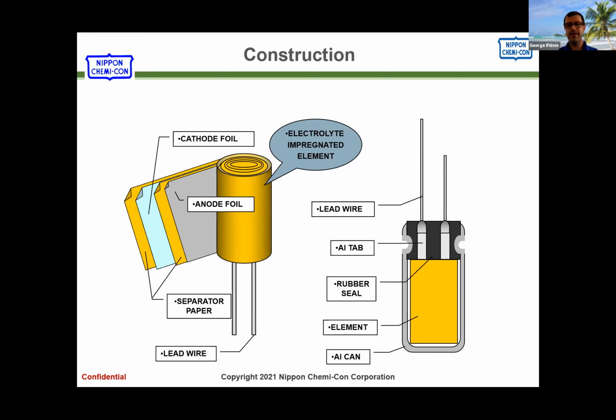That being said, there are things we can do to alleviate the problem. Especially on screw capacitors, many of our capacitors we can offer with what we call dimples, essentially dents. If you look at the gap between the yellow element and the outside can, we crush the can to mechanically lock the element in place. That construction - I don't want to say indestructible, but it's very difficult to have vibration problems with that type of capacitor.